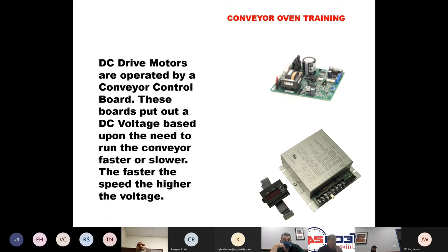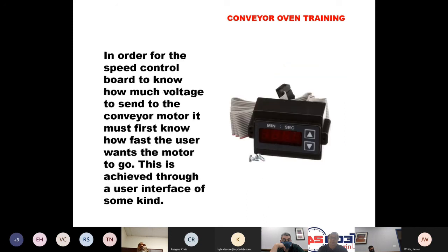DC drives. All DC motors are going to have some type of DC controller that's going to be looking at what the desired time has been set by the customer, and then it's going to create a DC voltage output to the conveyor motor. As that DC voltage increases, the motor will turn faster. When the DC voltage decreases, the motor will turn slower. In order for the speed control board to know how much voltage to send to the conveyor motor, it must first know exactly how fast the user wants the motor to go. This is achieved through a user interface of some kind. So basically, this is a little, I still call it a thumb wheel, but it's a digital display and allows the user to set the time in minutes and seconds that they want their oven to run at.